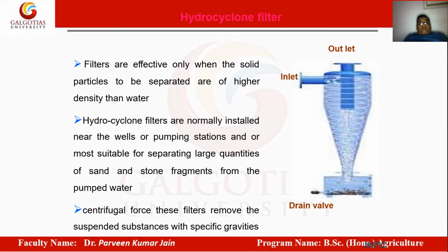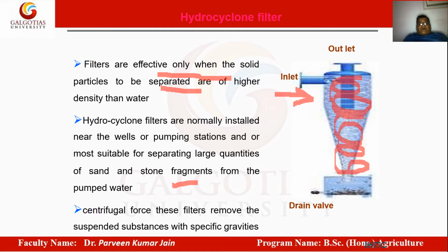The hydrocyclone filters are also very important. They work on the principle of centrifugation. Whenever the impurities of solid particles or sand particles are heavy, these filters are used, and they work as a centrifuge. The water has a centrifugal motion in the filter, and what happens? The solid material gets settled down here, the clean water is taken out, and the impurities can be removed from here.